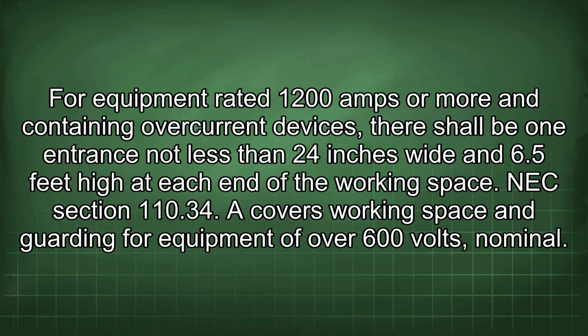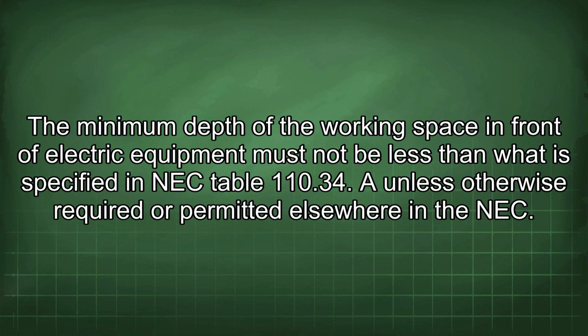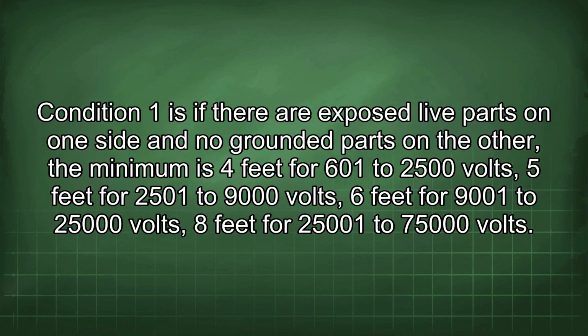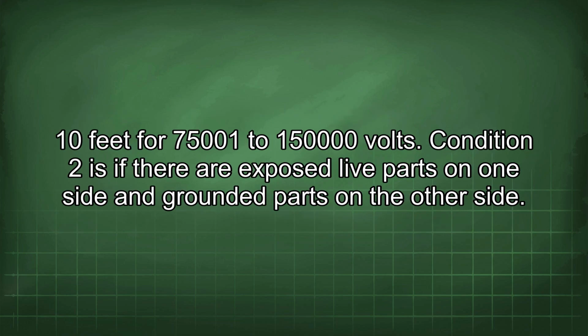NEC Section 110.34 covers working space and guarding for equipment of over 600 volts, nominal. The minimum depth of the working space in front of electric equipment must not be less than what is specified in NEC Table 110.34(A), unless otherwise required or permitted elsewhere in the NEC. Condition 1 is if there are exposed live parts on one side and no grounded parts on the other. The minimum is 4 feet for 601 to 2500 volts, 5 feet for 2501 to 9000 volts, 6 feet for 9001 to 25,000 volts, 8 feet for 25,001 to 75,000 volts, 10 feet for 75,001 to 150,000 volts.